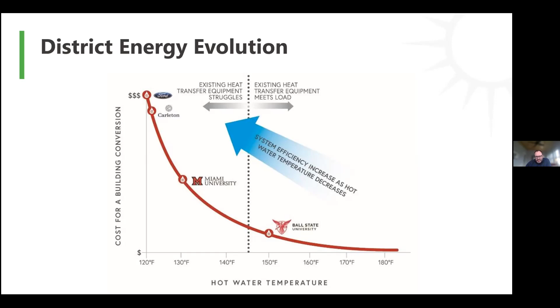I've shown a couple of projects here. We'll talk about the Miami project shortly, but you can see Ball State was designed at 150 degrees; it actually operates at 140 degrees supply temperature. We've had clients in the last five or six years go as low as 120 degrees Fahrenheit, and we currently have projects in design in New York City as low as 100 degrees Fahrenheit supply temperature—getting as close to low entropy, ambient heating systems as possible.